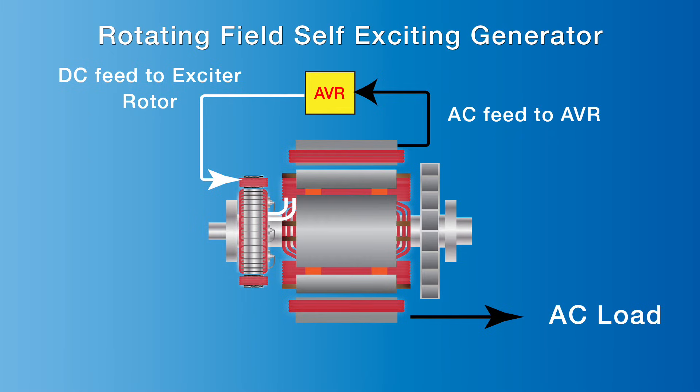A self-excited excitation system is a very effective method for regulating voltage output, especially for non-inductive loads such as heaters and lighting. However, a self-excited generator's output voltage is not the best option when a high percentage of the load is inductive, like electric motors. When started, they can reduce the generator's output voltage.